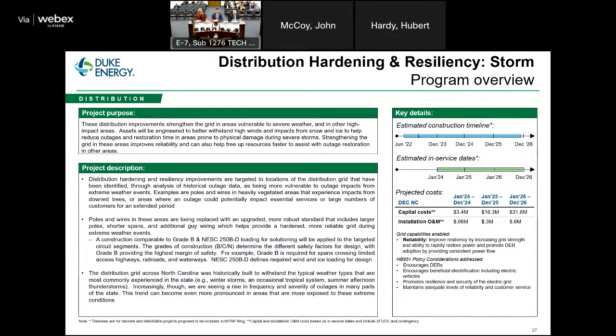Next is hardening and resiliency for storms. This is also data-driven, looking at outage history, specific storm cause codes, and geographic analysis of coastal areas more exposed to tropical events, and mountain zones more exposed to winter events with heavy snow and ice. There's a lot of information about grade B construction and NESC loading, but essentially this results in larger, stronger poles, shorter spans of wire between poles, and additional guy wires to withstand high winds and heavier ice loading in those exposed coastal and mountain zone areas.